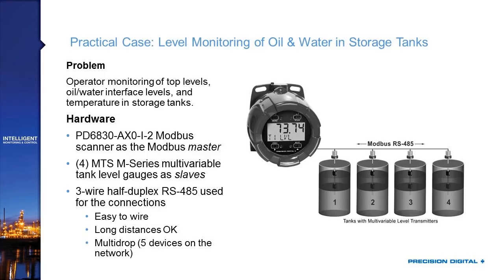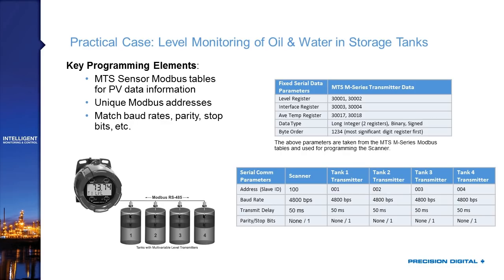Once wired with RS-485 going to all devices, they have to program the system. They use the MTS sensor Modbus tables to look up process variable data — a quick lookup tells them the register location for the level process variable, the interface level register, and the temperature register. As they step through programming the Modbus scanner, they know which registers to request and what information each contains. The Modbus instruction manual also provides data type information and byte order information for reference.